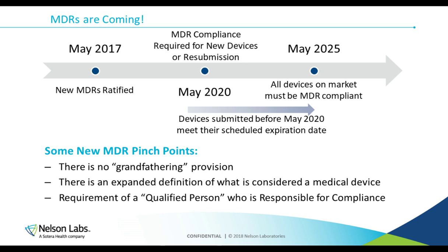So, I've read and reread the MDRs, which for me was a nail-biting, titillating experience. But it might not be the same for everybody. So I've distilled this body of literature down to a couple of bullet points there that you can see. One key point is that there's no grandfathering provision. So it's explicitly excluded that you could grandfather devices in. That means that even if your device has been on the market for a long time and had a CE marking in the past, that doesn't mean that you're okay to just do nothing and sail on through.